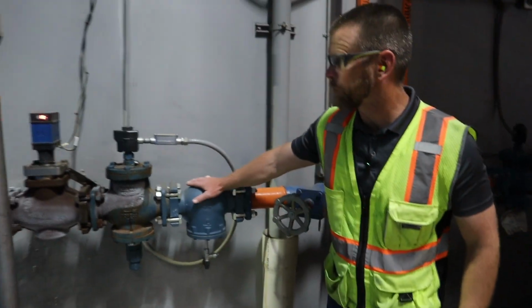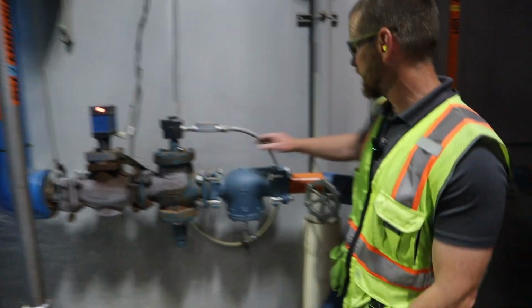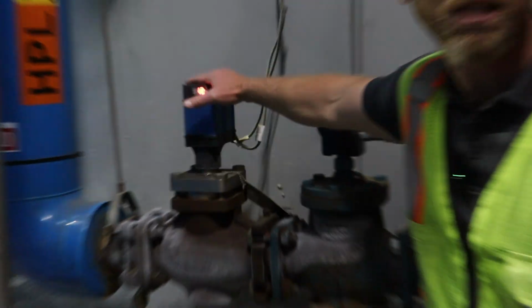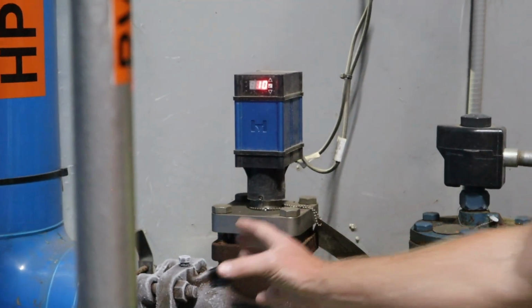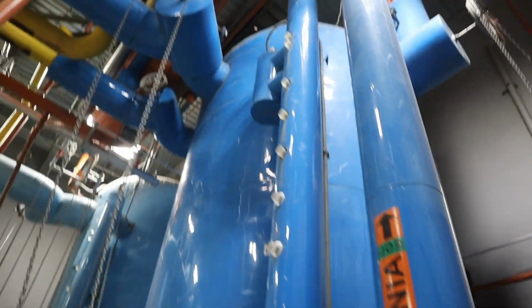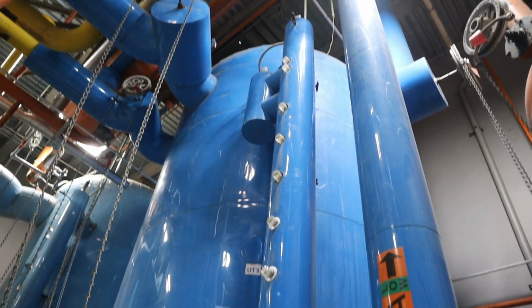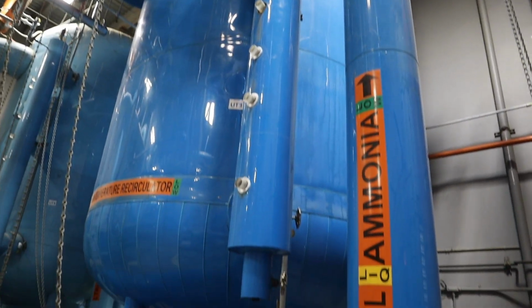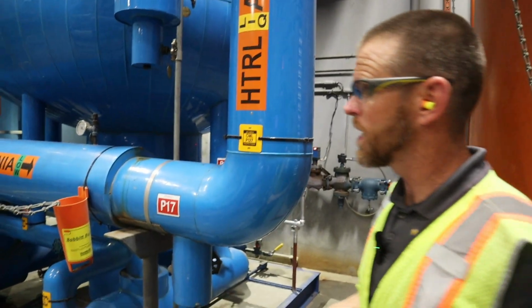So high pressure liquid from the high pressure receiver is piped through this valve group that goes through an isolation strainer solenoid, and then this is a motorized expansion valve where it lowers the temperature and pressure of the liquid as it enters the vessel. Both the motorized expansion valve and the solenoid valve are controlled by the level probe, which is on top of this level column. At the top of the level column, there's a probe going all the way through that's interlocked with those valves to precisely control the level in this vessel.